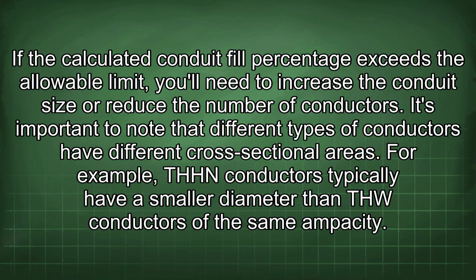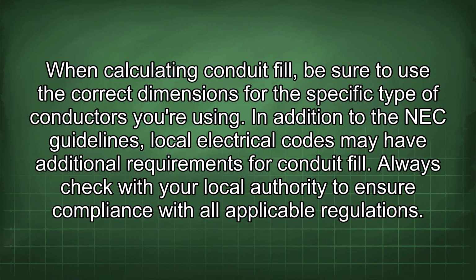the number of conductors. It's important to note that different types of conductors have different cross-sectional areas. For example, THHN conductors typically have a smaller diameter than THW conductors of the same ampacity. When calculating conduit fill, be sure to use the correct dimensions for the specific type of conductors you are using. In addition to the NEC guidelines, local electrical codes may have additional requirements for conduit fill. Always check with your local authority to ensure compliance with all applicable regulations.